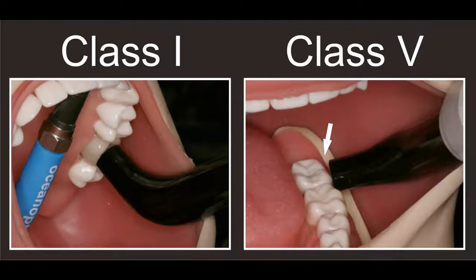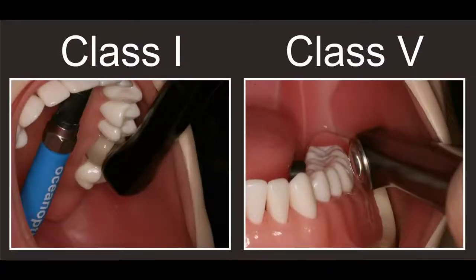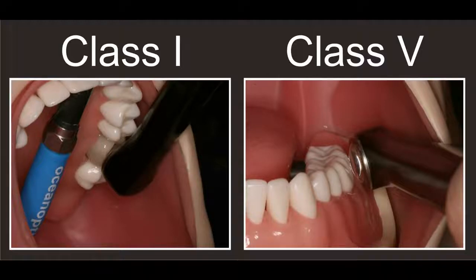Here we can see an example of a curing light with a light guide — note how difficult it is to access the Class I and Class V locations. In contrast, another curing light accessed these locations relatively easily. Even so, 20 operators using this particular curing light for the same curing time delivered between 4.4 and 17.4 joules per centimeter squared.